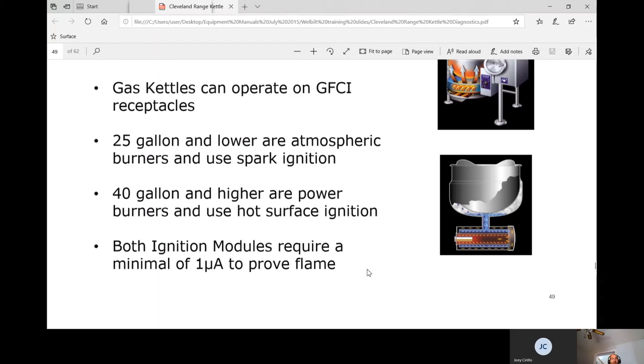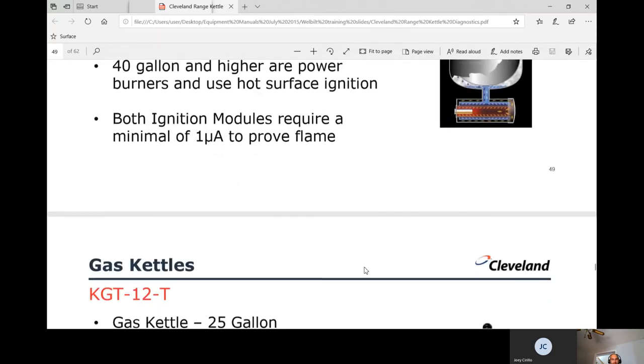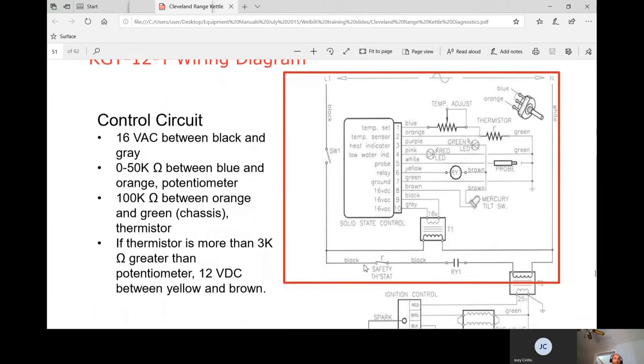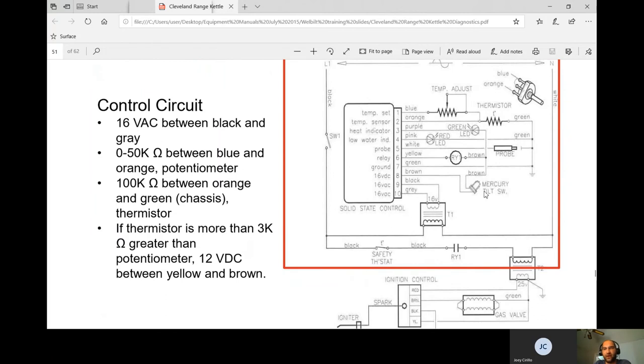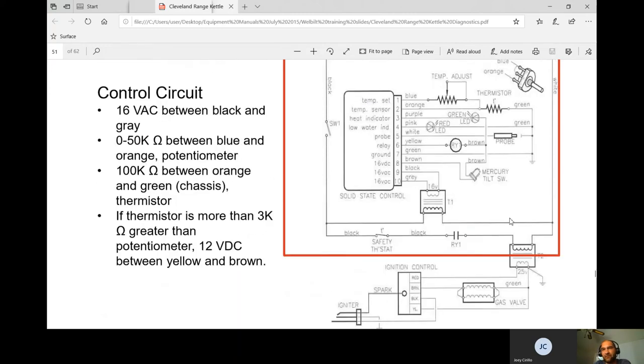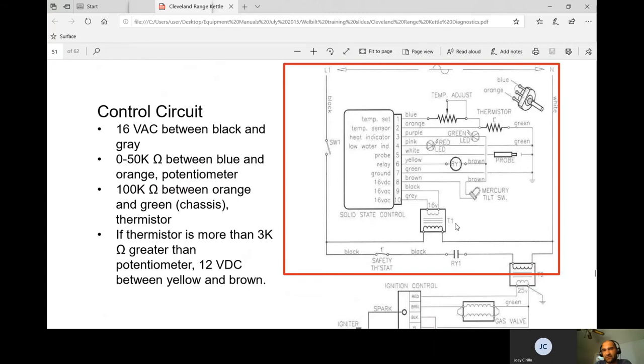Both ignition modules require a minimum of one microamp to prove flame. For the 25-gallon model, the control circuit is the same as the electric kettle — the only difference is when the RY1 coil closes its contacts, we go through a transformer and get 24 volts out to the gas valve instead of to a heating element. Everything above that point is identical to the electric kettle circuit.